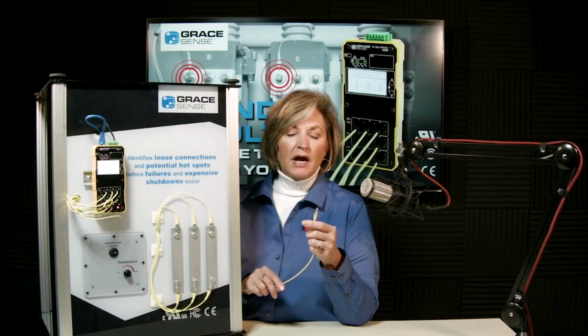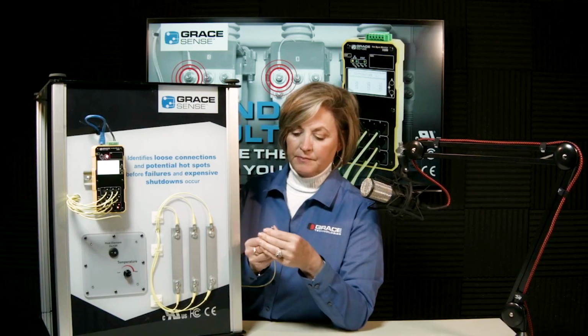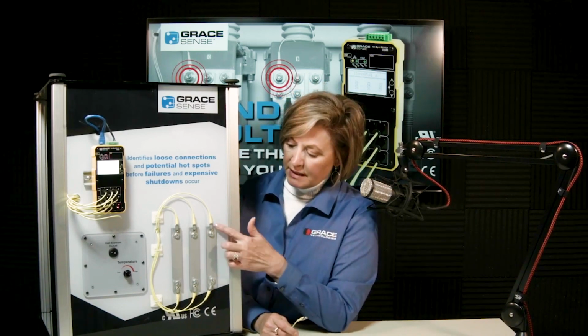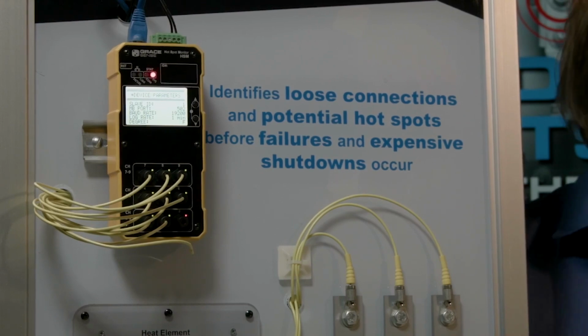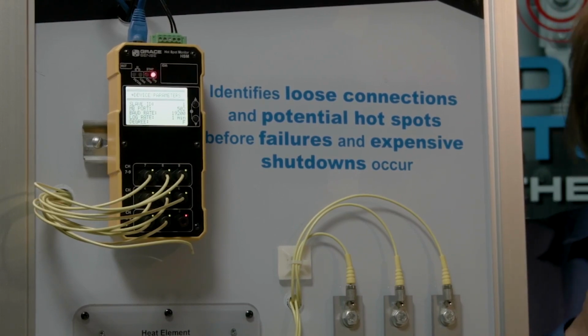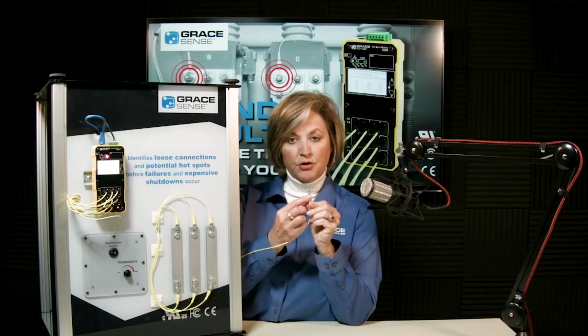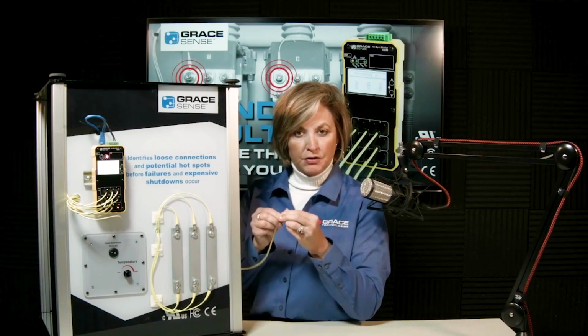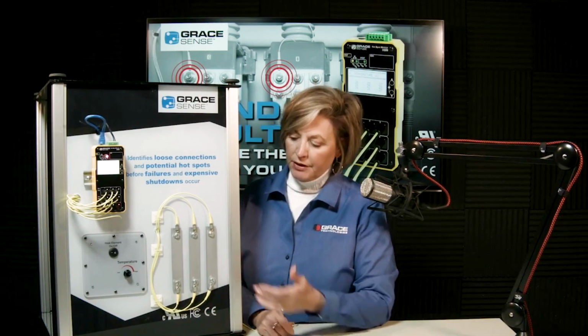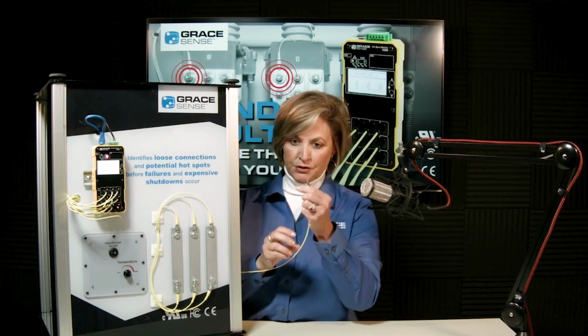The attachment of the fiber to a bolted location, what we call a fixture, is really nothing special. It's a ring lug, and the only difference is that the end of it needs to be a 6-gauge wire opening, because that's the size of the probe. There's a piercing set screw inside this probe tip that actually secures it nice and tight into the lug itself. But there's nothing special about the lug. Again, we use tin-plated copper, but we just want it to fit snug so that the heat will transfer to the probe itself.